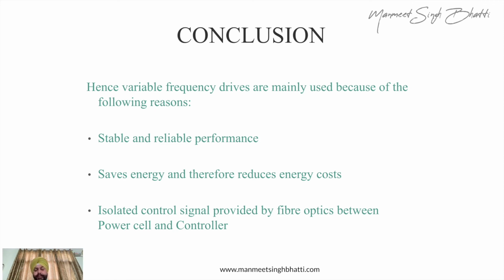Next is, it saves energy. Definitely it saves energy, because at the end of the day you are reducing your speeds, you are changing your frequency. Based on that, your total energy cost, the total ownership cost of the complete system goes down. And you don't have to calculate the energy saving in the field for say 6 months or 5 months, because the VFDs work for 5 years, 6 years, 7 years. So based on that, you can understand even 5% of saving for the next say 5 years is going to be a big level of saving for you, and it actually keeps your motors protected.